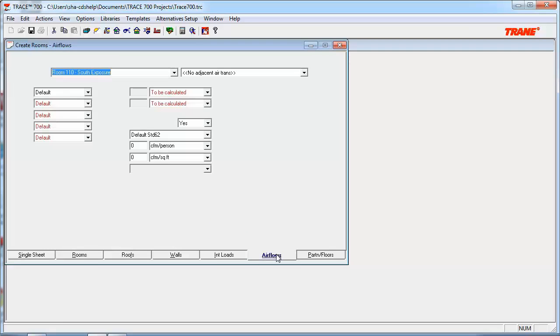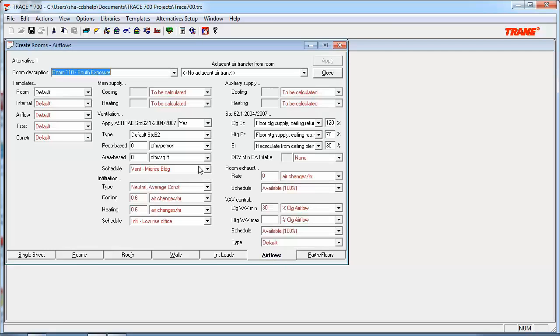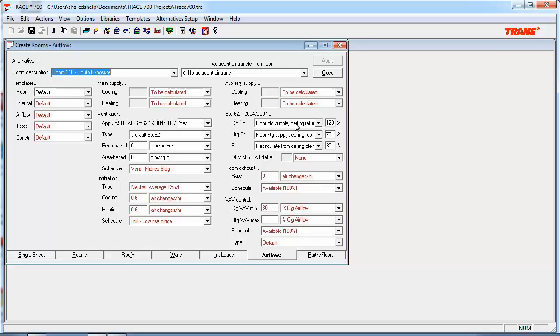Moving on to the Airflows tab, and if you're applying 62.1, this is where you can input the zone distribution effectiveness of the supply. For a UFAD system, you would want to select Floor Cooling Supply and Ceiling Return, and obviously you'd want to do the same for the heating portion as well. This changes the ventilation effectiveness since supply air is delivered at the occupant's feet, which may lower or increase the overall total ventilation rate depending on which mode you're in of cooling or heating.